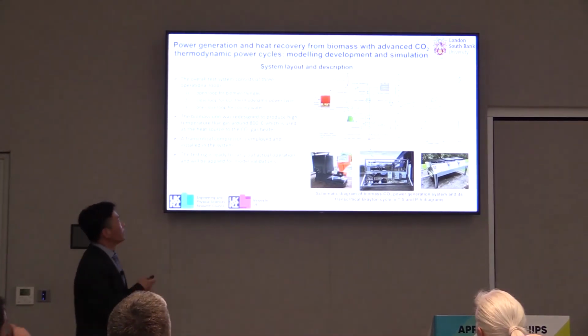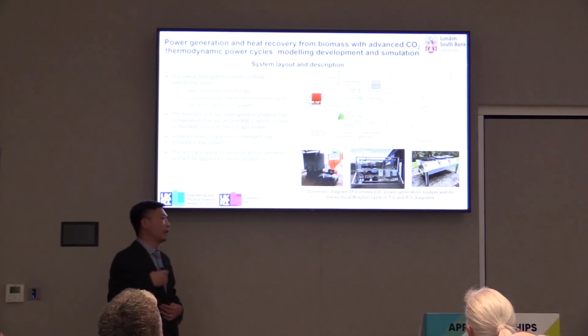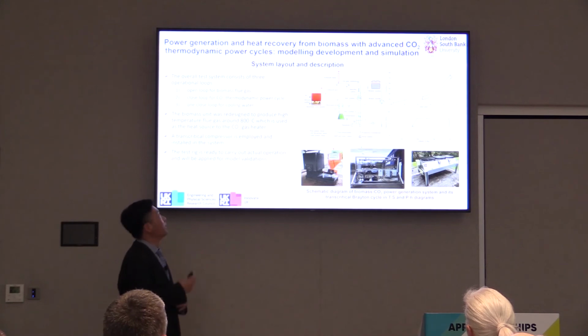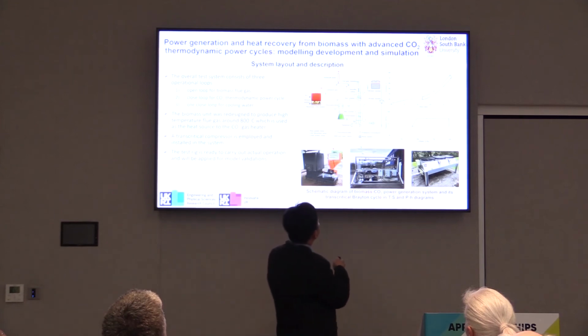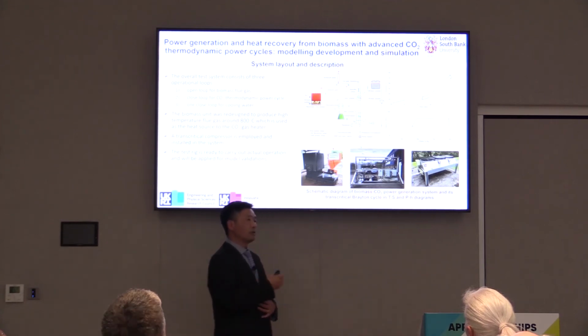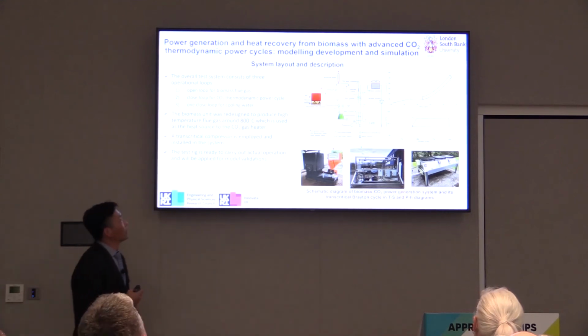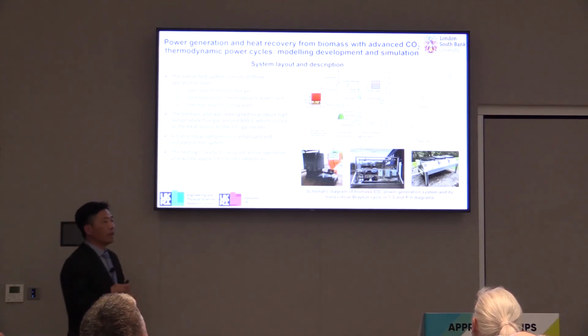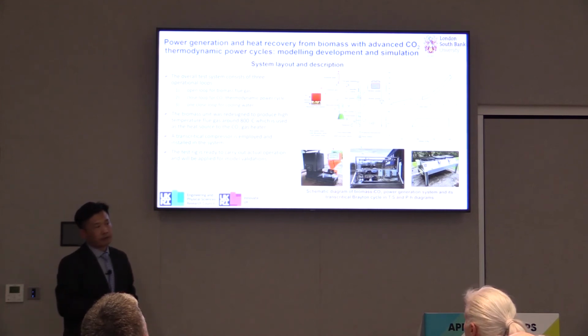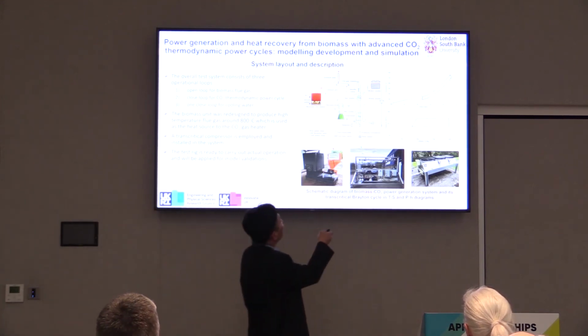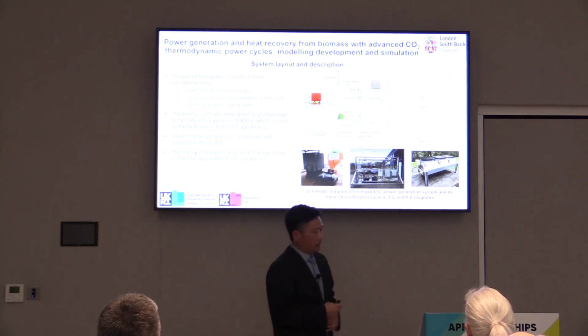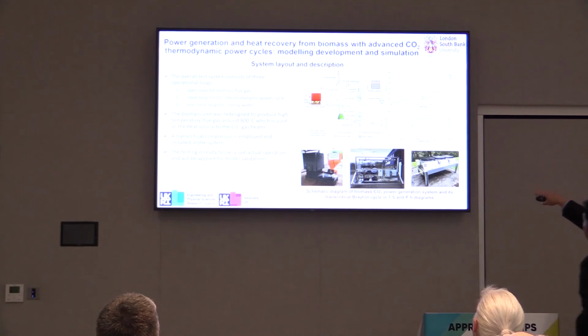And this flue gas is used to heat the CO2 gas heater directly, instead of using a heat transfer medium, so that the CO2 can be heated up to about 500 degrees C. And here, instead of using the air-cooled condenser for the ORC and the transcritical CO2 system, we're using a water-cooled condenser. We have a cooling water loop here.